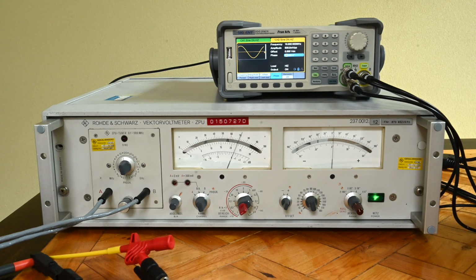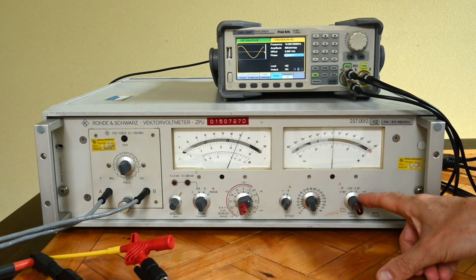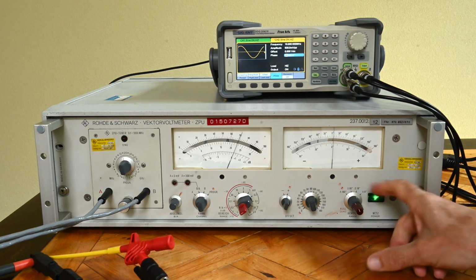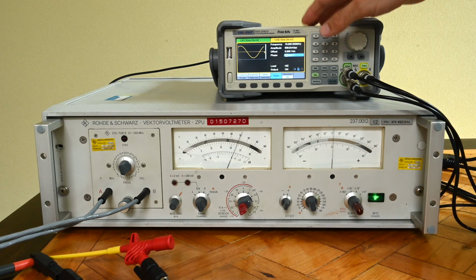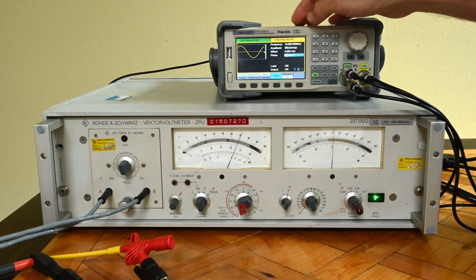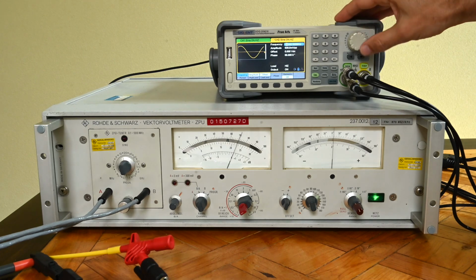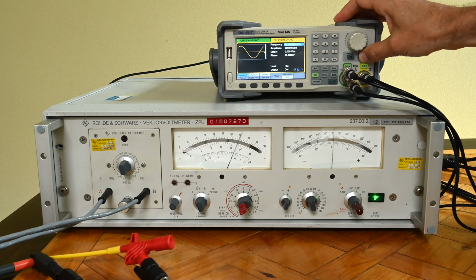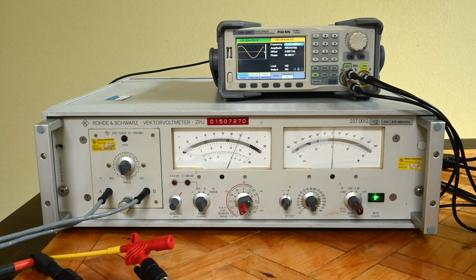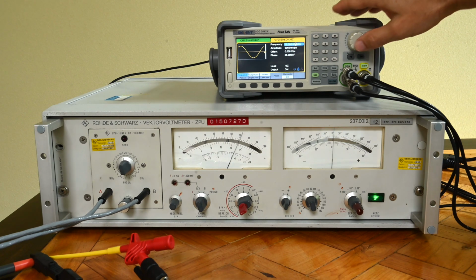Now, another thing that we will be able to use the device for is to look at differences between frequencies and a frequency reference, for example. So let's quickly go into that. We're back at the 180 phase screen here, and instead of just introducing a phase difference, I'm going to introduce a different frequency. I've got 10 megahertz, and I'm just adding a single hertz to the 10 megahertz. So that's a 1/10 of a millionth difference here.